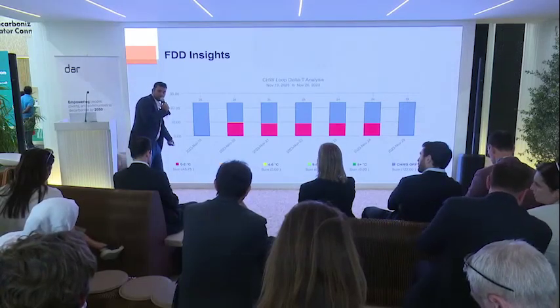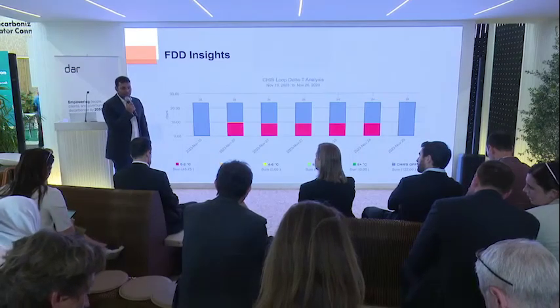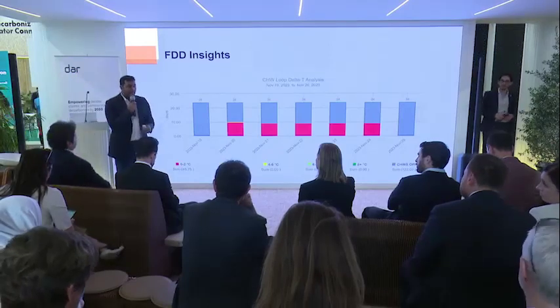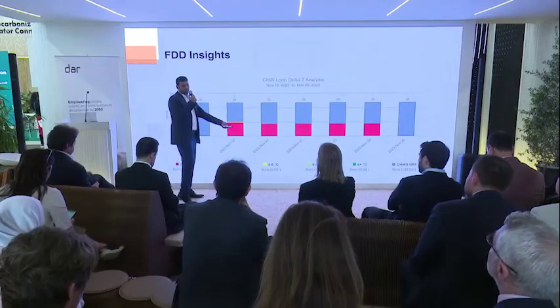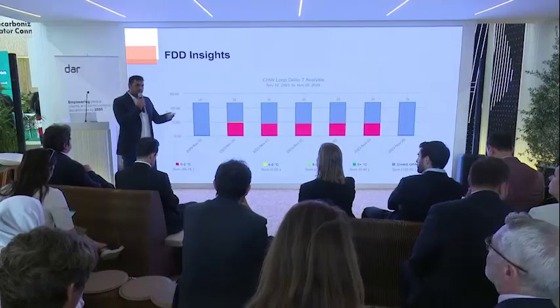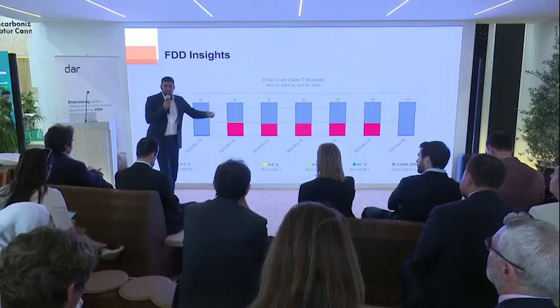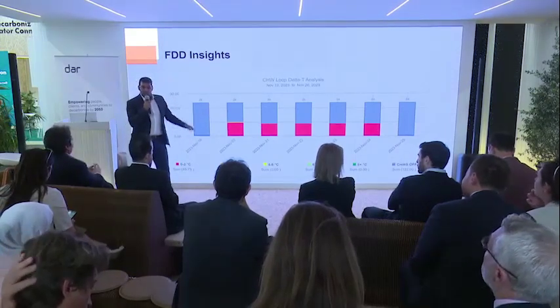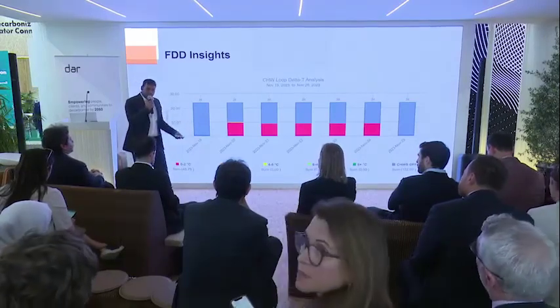The temperature differential between the two sensors is really low. So you don't really have much happening in terms of cooling being provided. More importantly, cooling being needed. And because cooling is not needed, why would you run your chill water system, right? That's the whole idea, in that you can now use this information, present it to the guys, the girls running the building, and say, hey, you have an opportunity here to now configure the system, change the sequence of the system so that when your building does not have enough demand, then you can actually turn down the system.